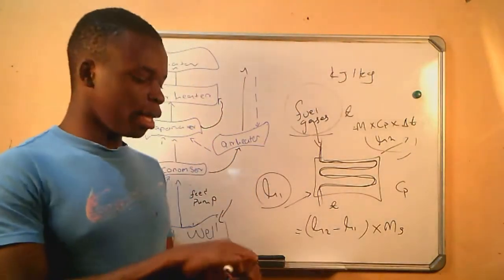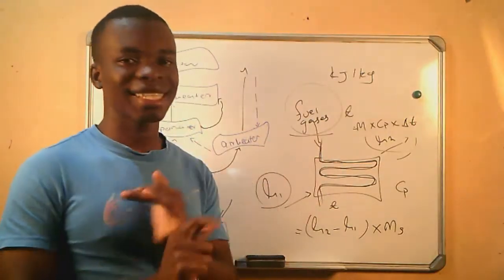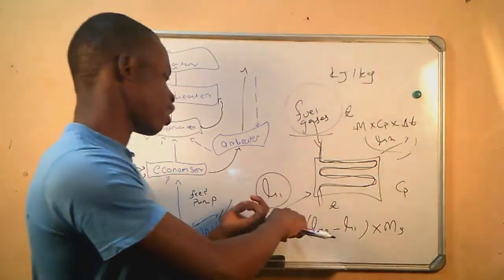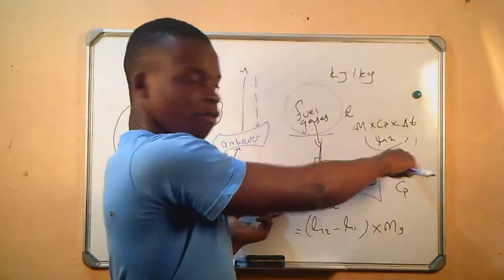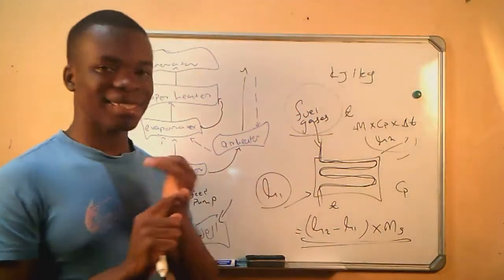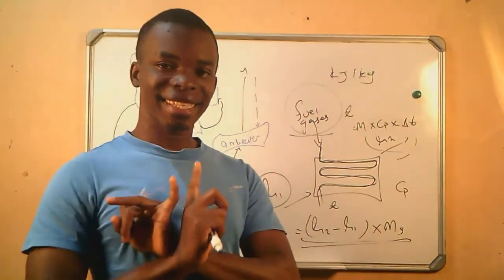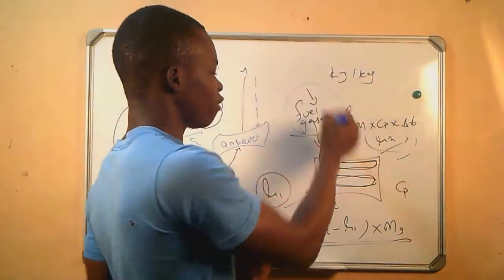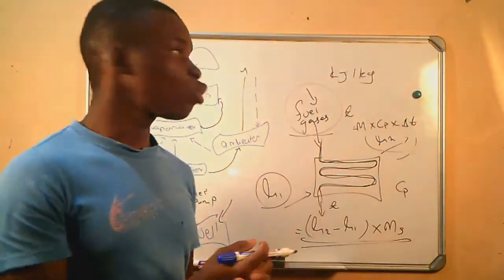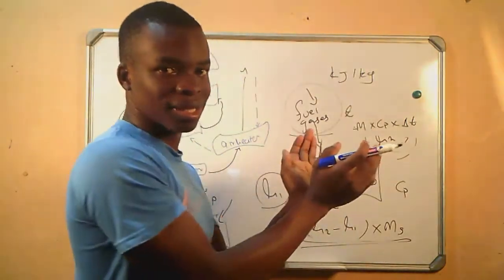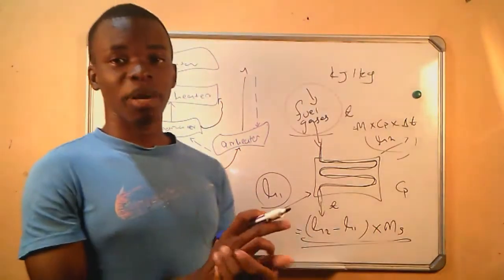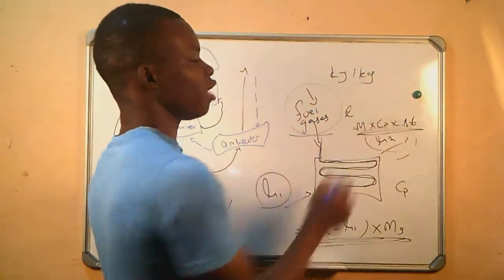Questions might come in two ways. They might ask you to calculate the heat that is gained in the economizer — that refers to the heat gained by the feed water from the economizer. Or they might say calculate the heat that is lost in the economizer — that refers to the heat lost by the fuel gases at the economizer. We know that the heat lost by the fuel gases equals the heat gained by the feed water. Either way, you can use any formula as long as you have the information, but always try to use the enthalpy formula first.